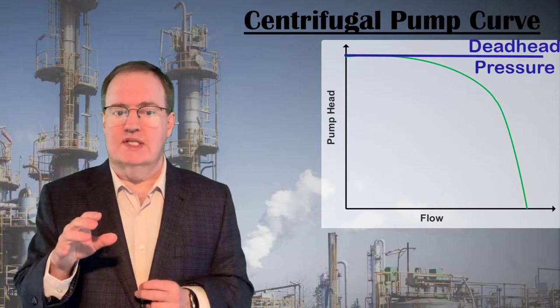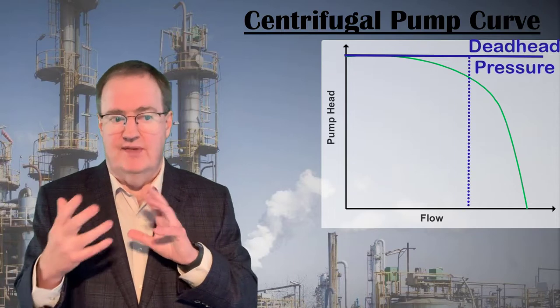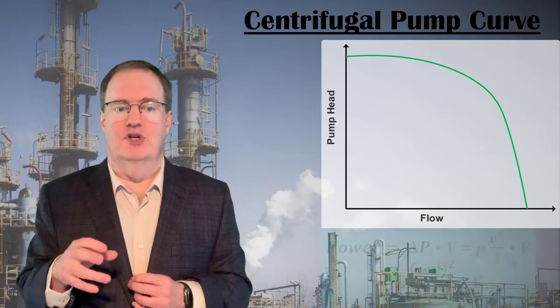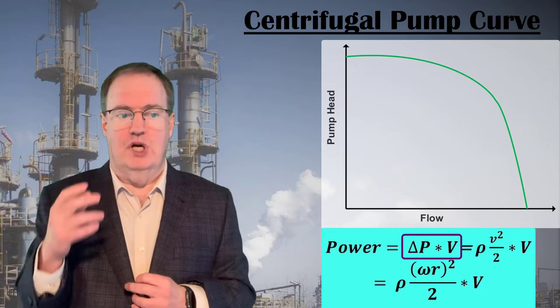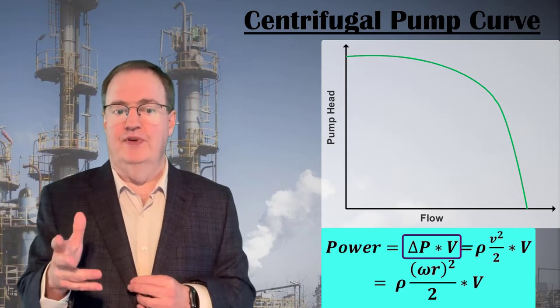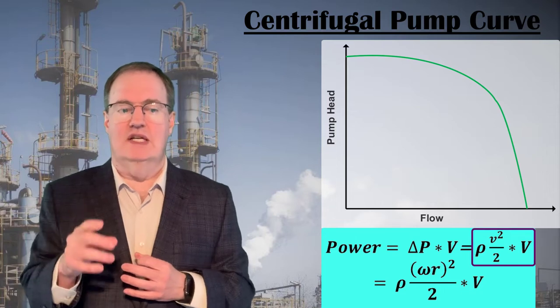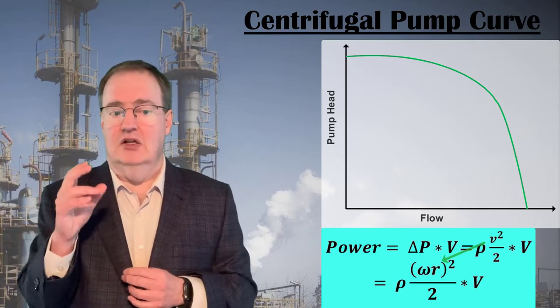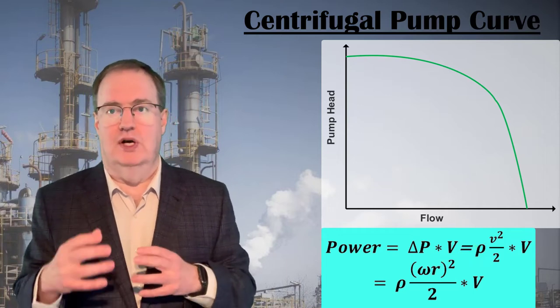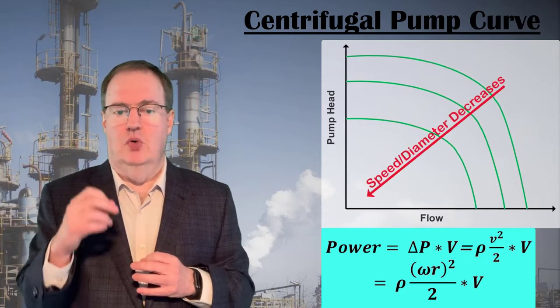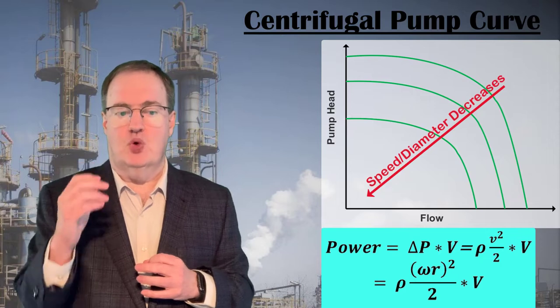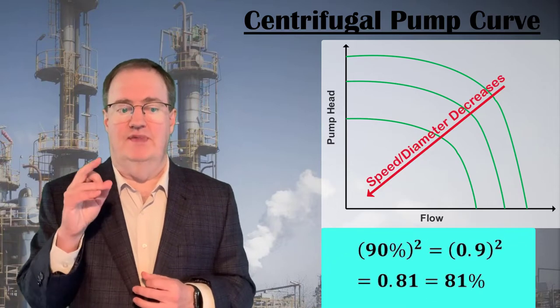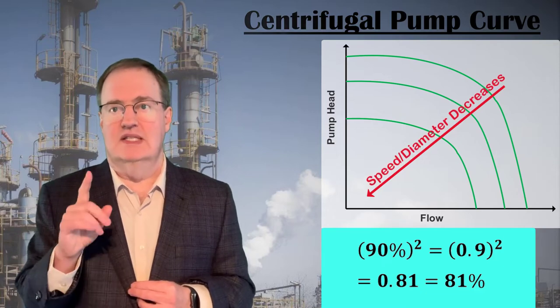Note that the pressure is close to constant at the no-flow or deadhead pressure up to 60% to 70% of the pump's flow capacity. This is the region we usually find ourselves operating the pump in. The power that a pump delivers — or at least an ideal frictionless pump — is the product of the pressure increase delta P and the volumetric flow V. If we convert the pressure gain into the product of density and velocity squared over 2 via Bernoulli, and then convert the velocity into the radius R multiplied by the angular velocity omega, you can see that the power is proportional to R-squared or omega-squared. As either the impeller diameter or the pump speed decreases, the pump power will decrease with its square. This is important to remember with variable speed pumps: a centrifugal pump running at 90% of its top speed delivers only 81% of the power.